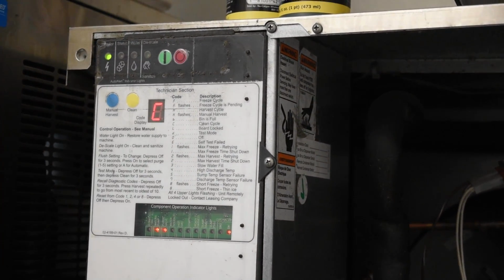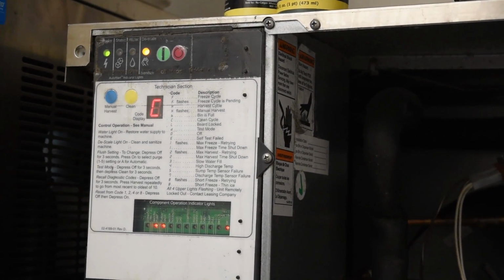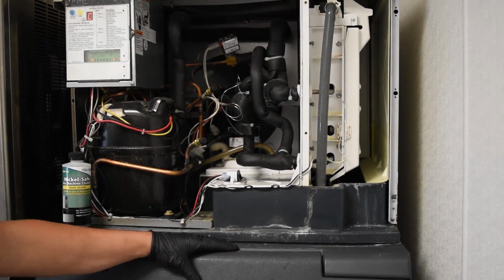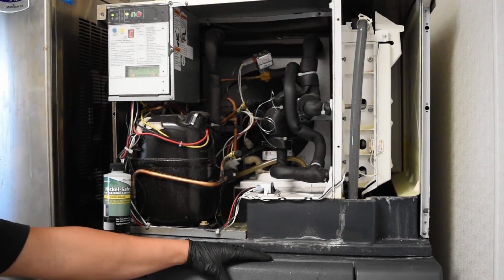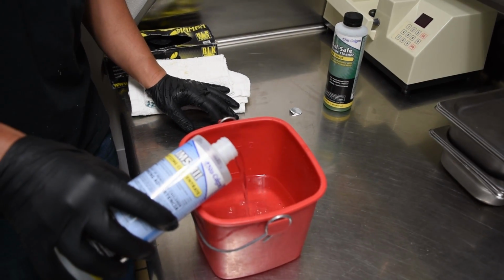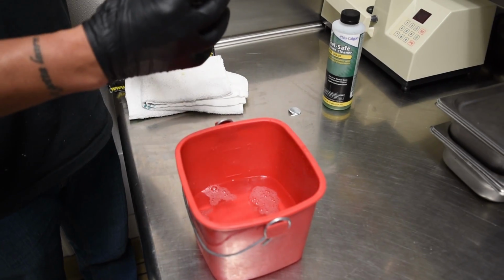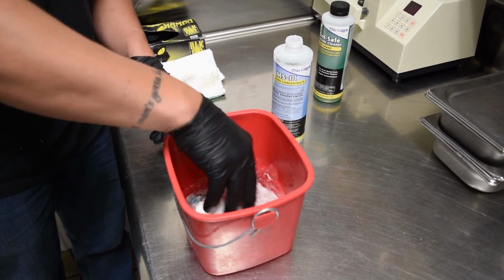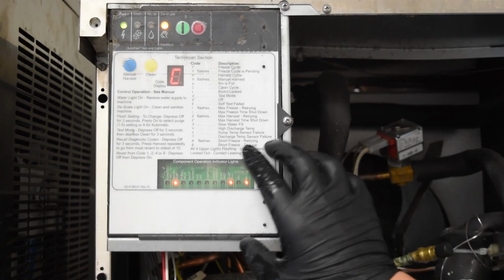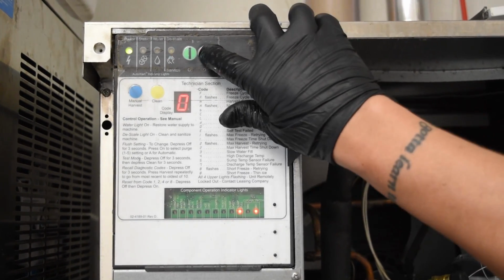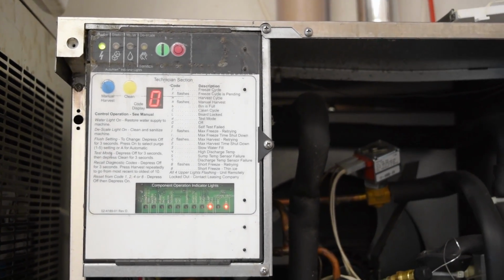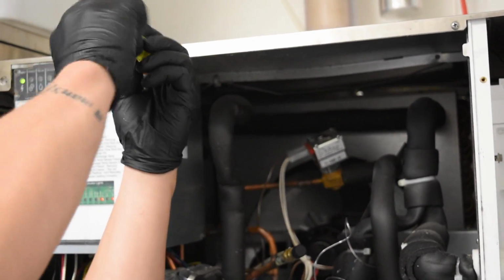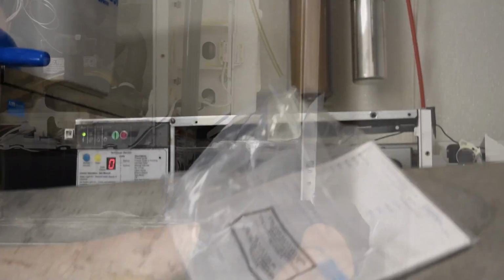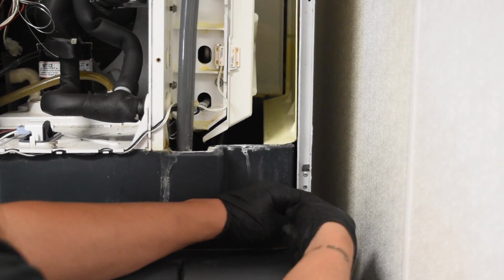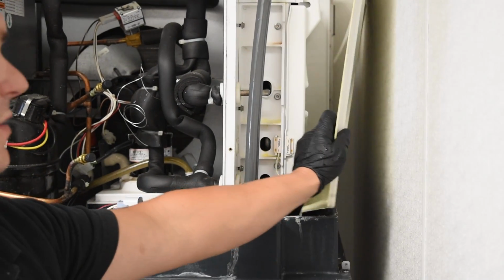yellow. The ice machine will begin expelling the chemical through a clean water purging process, which will also need to run for 20 minutes. During this 20-minute purging cycle, prepare a sanitizing solution using 12 ounces of water and 1 ounce of sanitizer. After the 20-minute clean water cycle is complete, press the red off button. In order to sanitize all of the parts, remove the top panel screws and set the top panel aside. Next, remove the bottom screw and set the inner and outer side panels aside.